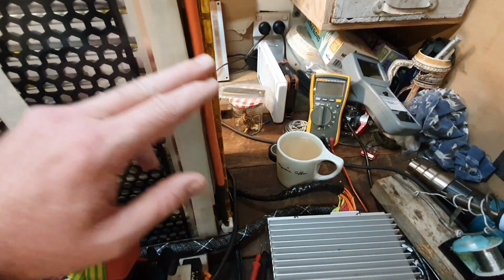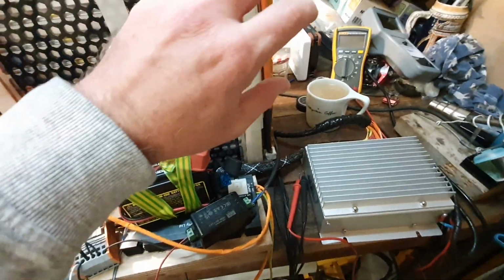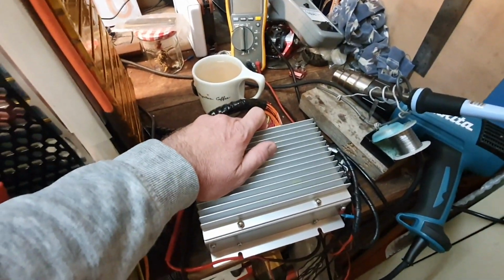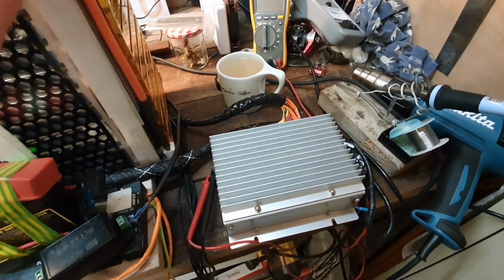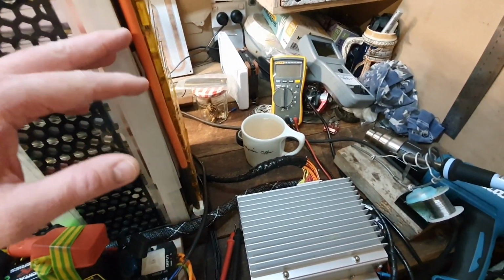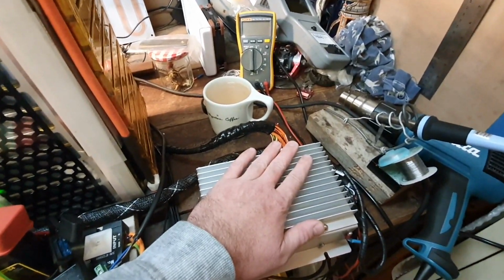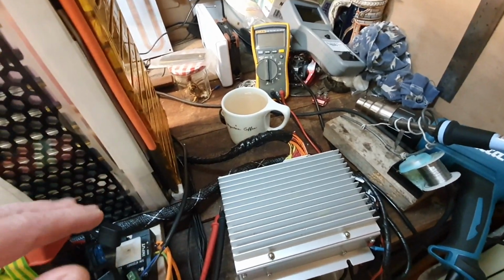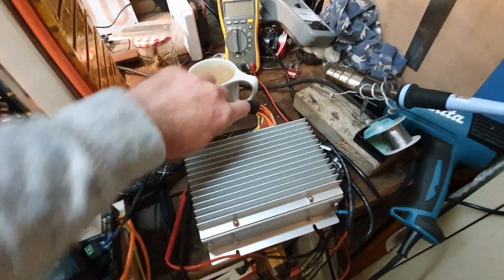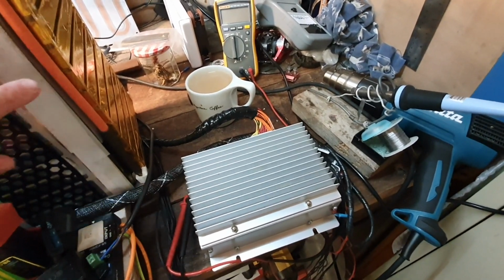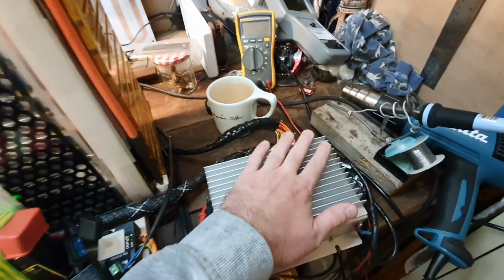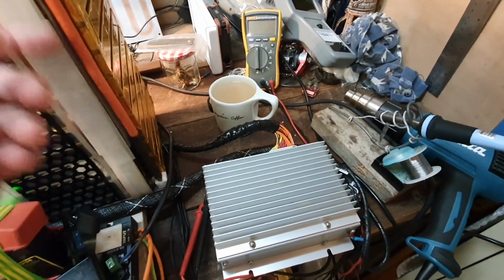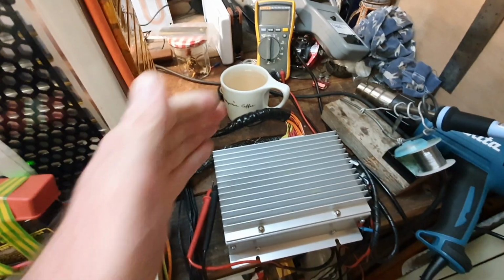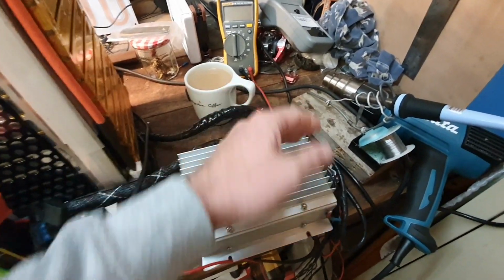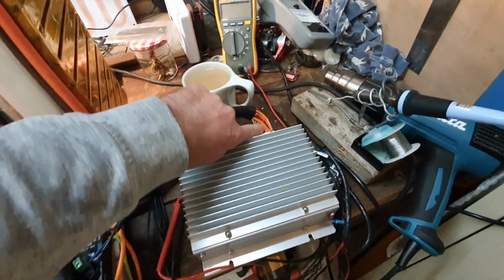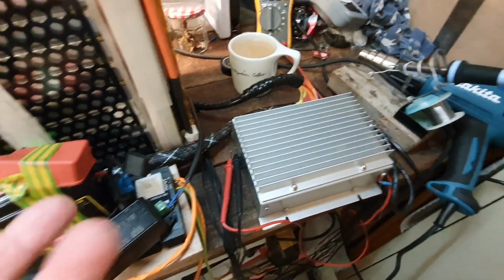It allows you to split your pack up into component parts and put a fuse between them. Effectively, one of the cell taps is duplicated on a single cell, or at least that's what the BMS sees if you're wiring these all in series with no fuses. What happens is if you're putting fuses in, you put that negative one and then the next one along between the fuse, and that way the BMS has each group completely isolated if you pull the fuse out, and it doesn't destroy the BMS by running a huge amount of current through these tiny cables and frying all the electronics inside. That's the intent behind it.